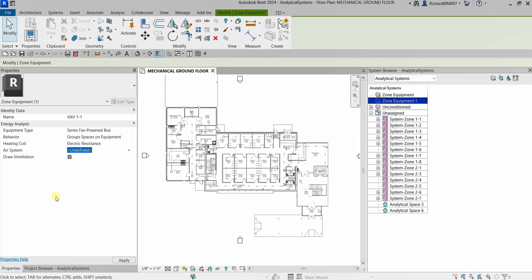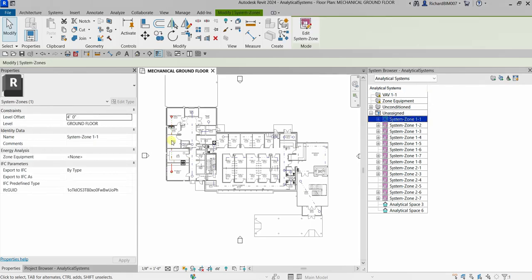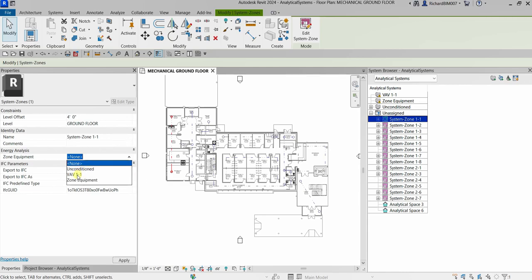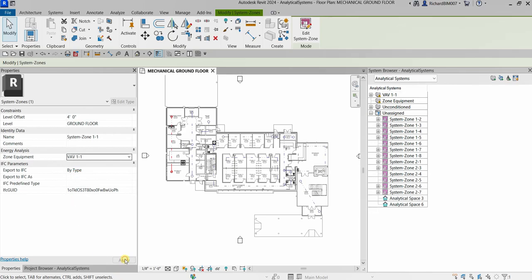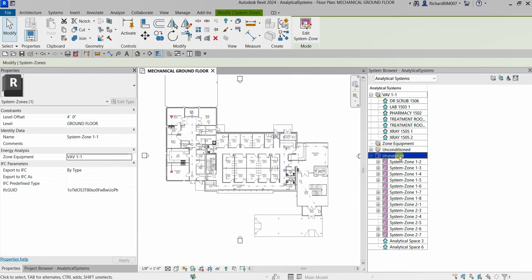After creating the zone equipment, select 'System Zone 1-1' in the system browser, then set its zone equipment to 'VAV 1-1' — the one we just created. Click Apply, and you will notice System Zone 1-1 is no longer under 'Unassigned' because it is now assigned. Expanding VAV 1-1 shows the analytical spaces underneath.